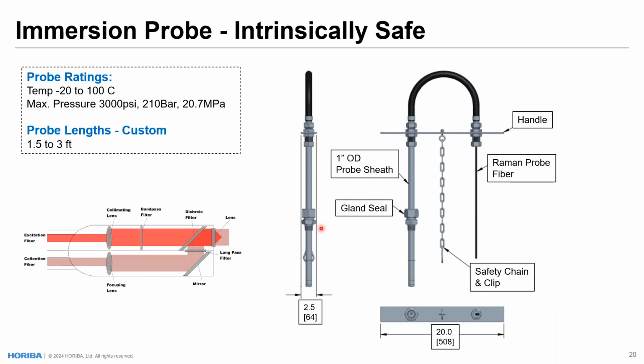Next is our immersion probe. The immersion probe we also call intrinsically safe, and this can be installed directly in line into your process stream. The probe here is rated up to 210 bar or up to 3000 PSI of pressure, and a temperature range of -20 to 100 degrees Celsius. The probe length can be customizable between 1.5 to 3 feet, and that would be this distance here after the gland seal.